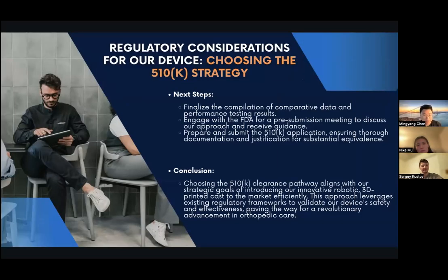So for the next steps, we will finalize the compilation of the comparative data and the performance testing results, and we will engage with FDA for a pre-submission meeting to discuss our approach and receive guidelines. And next, we will prepare and submit the 510(k) application, ensuring thorough documentation and justification for substantial equivalence.